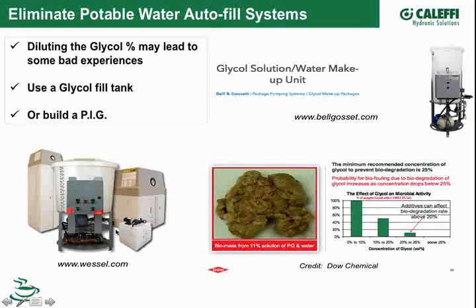Glycol always has to be sealed too. You can't keep it in a container that isn't tightly sealed, or left open, because then this biogrowth can happen if you've got air. Above the water line, those tank walls will be wet, and that's a ripe area for biogrowth. So, yeah, that's a very good point.